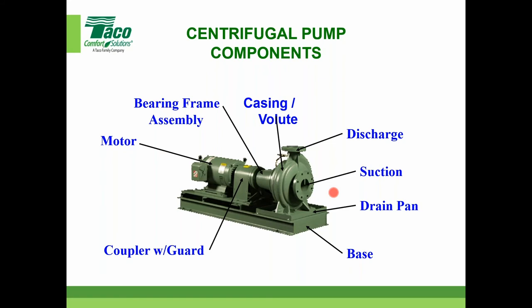So in other words, I'll take the discharge gauge. Let's say the suction pressure was 40 pounds and the discharge was 60 pounds. I'll swap the two gauges to make sure that they're reading their corresponding values and then put them back again. That way I know the gauges are accurate if they're both reading the same value for the same location. You're correct, one gauge with valves eliminates the difference between the gauges, but it's more convenient to have two gauges so you can see them simultaneously. So there are pros and cons to each.